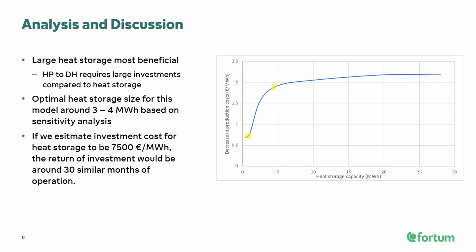So if we estimate the investment cost for heat storage to be around 7,500 euros per megawatt hour, the return of investment would be around 30 similar months of operation if 4 megawatt hours of storage was chosen.